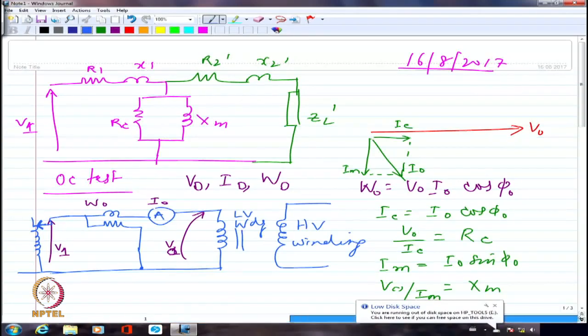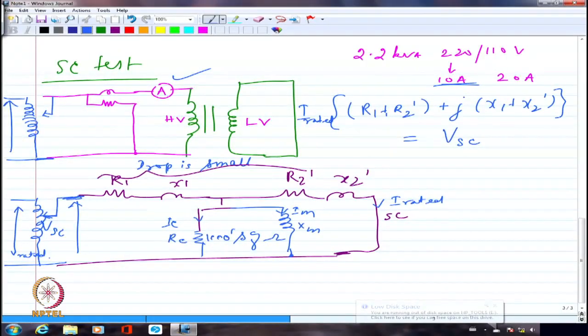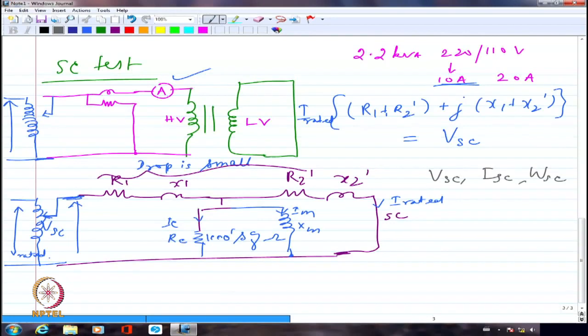So let us look at now the short circuit test calculations. So I am going to have VSC, ISC and WSC. WSC will give me only the real power quantity, which will be very clearly ISC square multiplied by R1 plus R2 dash. Only two resistances are there and only they can dissipate real power. So what I get actually as WSC will be ISC square multiplied by R1 plus R2 dash. Right? And from here, I should be able to get what is the value of R1 and R2 dash.